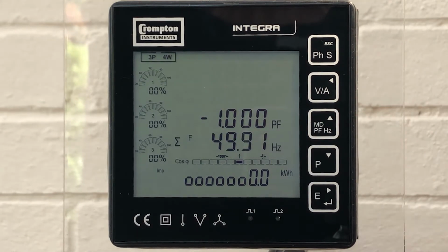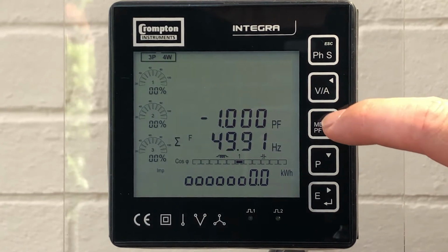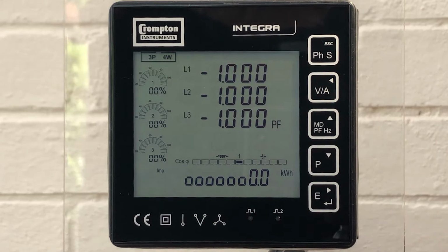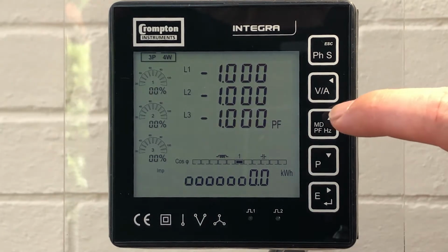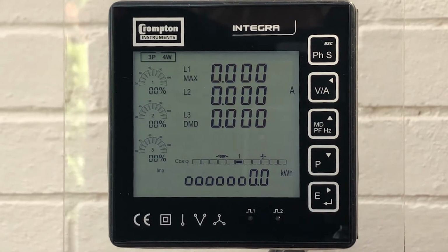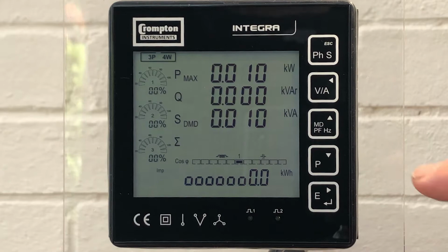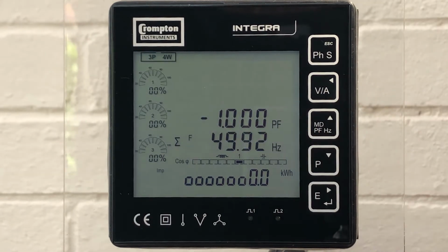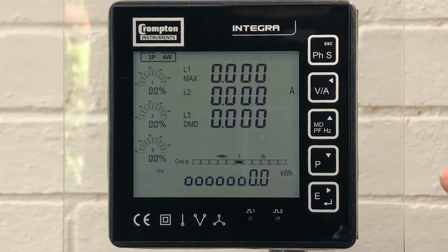A press of the MDPF button shows us the power factor and frequency of the system, the power factor per phase, the maximum demand current per phase, and the active power, reactive power and apparent power of the system.